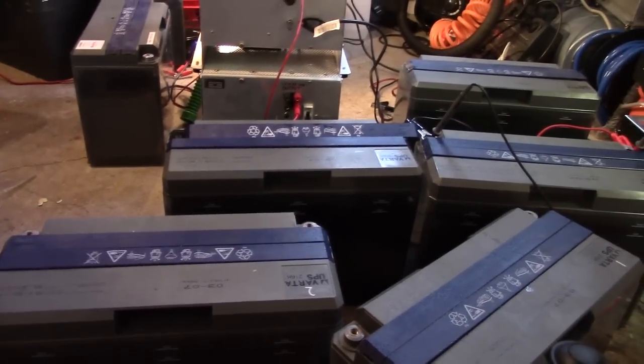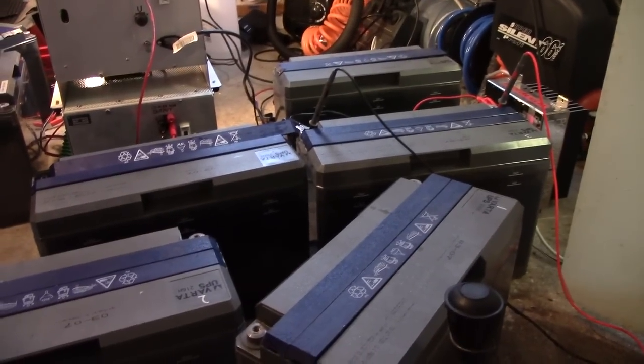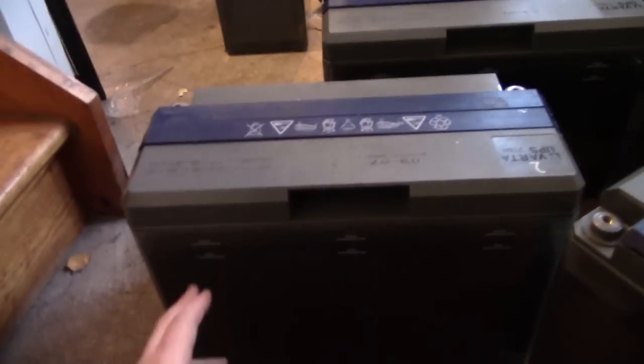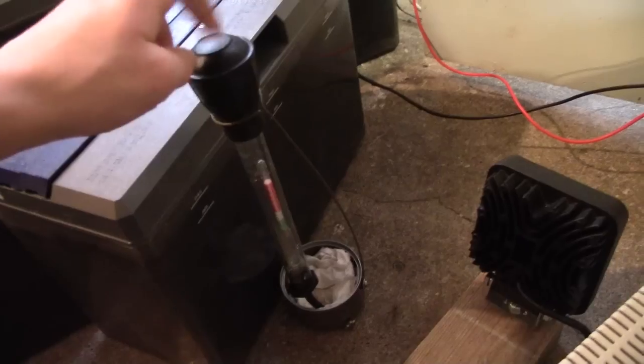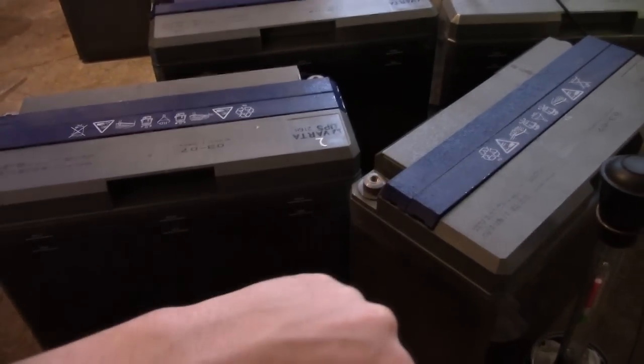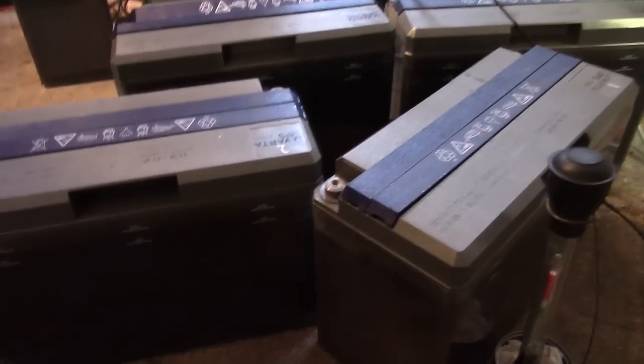And that's good and bad — they are in very good nick in some ways, but they have grown rather unbalanced over the years. Some cells have pretty much every second cell with very low specific gravity while every other has very high. But these two turned out quite well; I've cycled those and they came out at about 120Ah each, which is pretty good for their rated capacity of 114Ah — to say the least, after a decade.